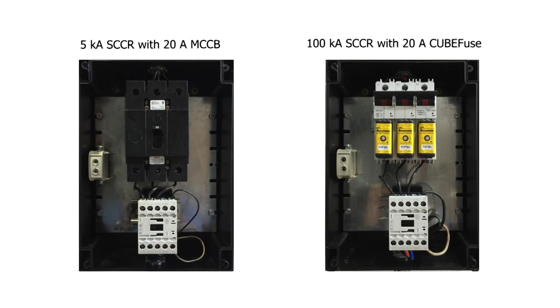Here we have an enclosure with a contactor rated 5,000 amps protected by a non-current limiting overcurrent protective device. This enclosure can only be applied in a system that can deliver no more than 5,000 amps of fault current. But what happens if it sees 65,000 amps?